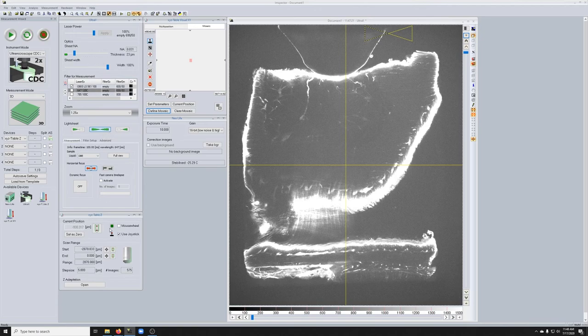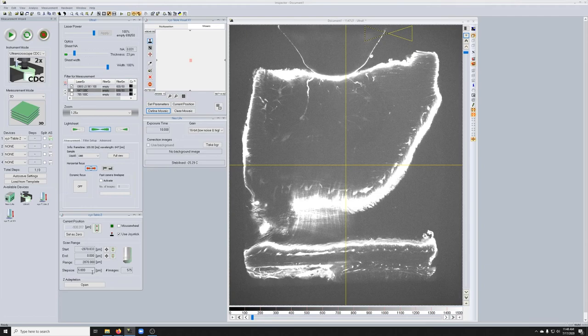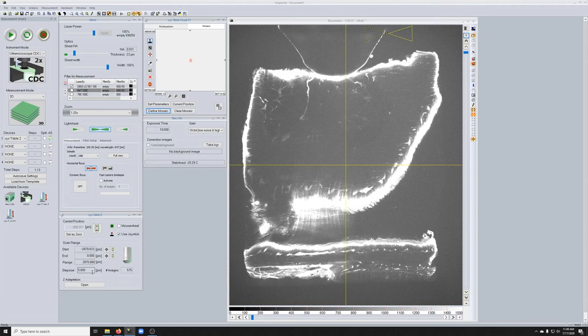What else do we need? We need a start and an end for the Z-Stack, which we set at the very beginning, and we need a step size. If you're imaging at high resolution with high sheet NA, a good step size is 2 microns. If you're doing anything else with lower sheet NA, a minimal step size to check is 5 microns.